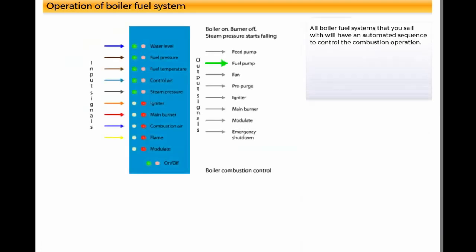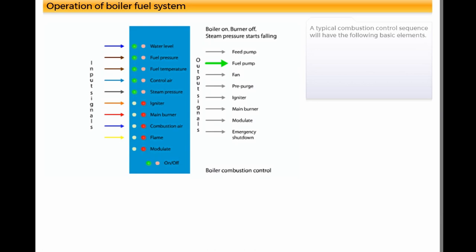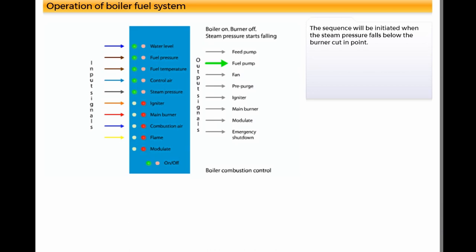All boiler fuel systems that you sail with will have an automated sequence to control the combustion operation. A typical combustion control sequence will have the following basic elements. The sequence will be initiated when the steam pressure falls below the burner cut-in point.